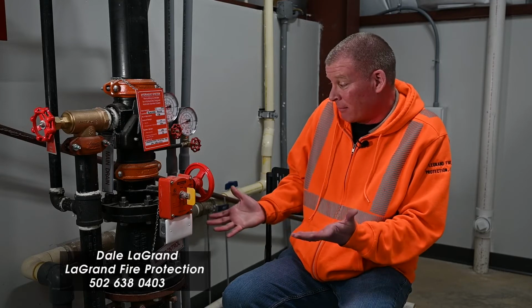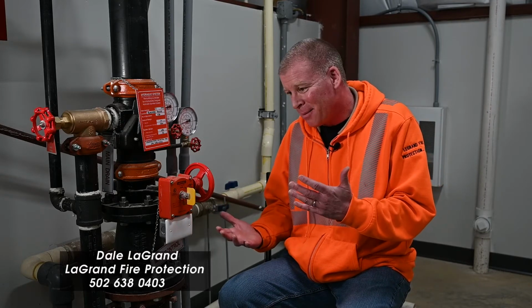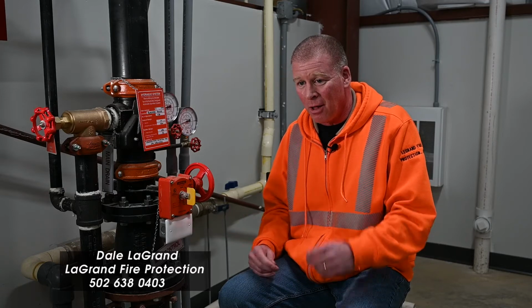Other than that, you really don't have to do anything to the sprinkler system. If you see a head that's dusty in the office, you take a damp cloth and just wipe it off. You never use any chemicals on it because you could mess with the bulb that's in the sprinkler heads. Other than that, you need to have an annual inspection. That's something we can do. You just need to have a sprinkler contractor look at it once a year and come by and make sure your alarms are functioning and that everything's intact. Other than that, you don't have to do anything else with it.